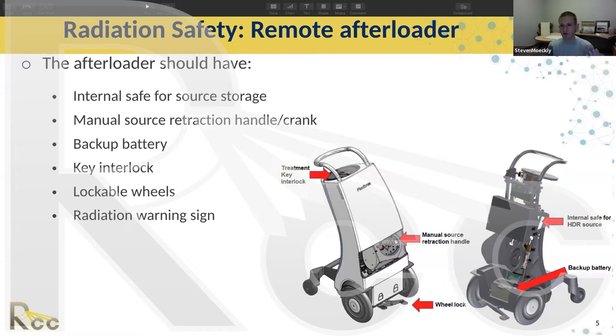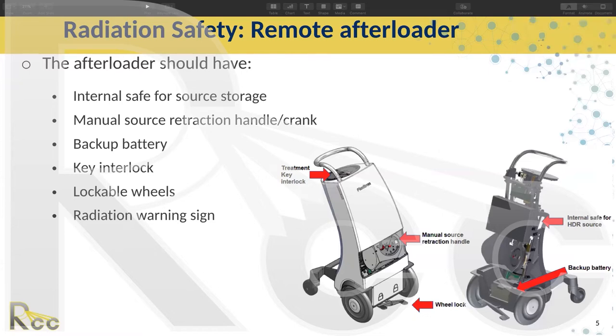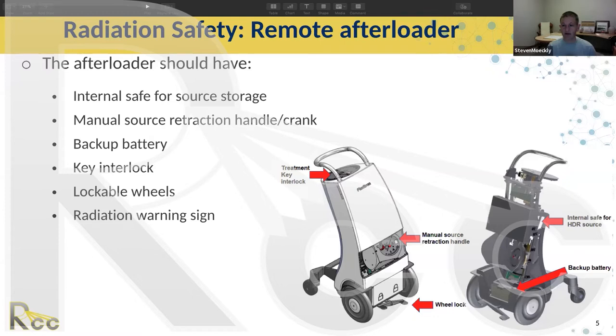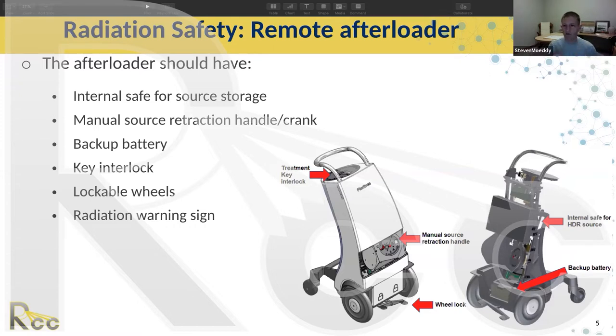A backup battery is very important, especially in areas where the reliability of the power grid is not as great. If the power goes out, the backup battery can retract the source back into its safe without issues. We test that on a daily basis, and that should be part of your daily procedures. We have a switch wired in — we switch it, it cuts the power to the machine, and after about 10 seconds it retracts. There should also be a key interlock and lockable wheels.